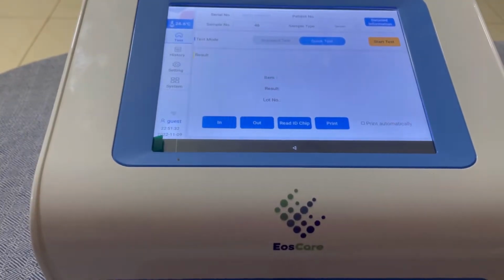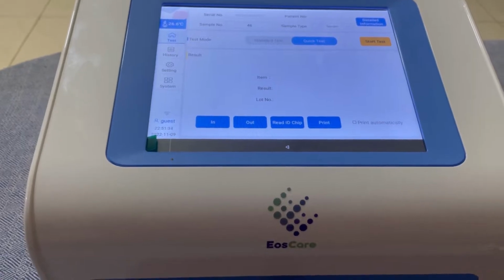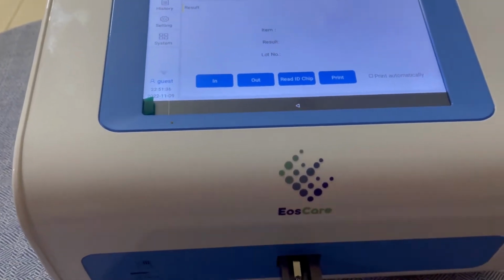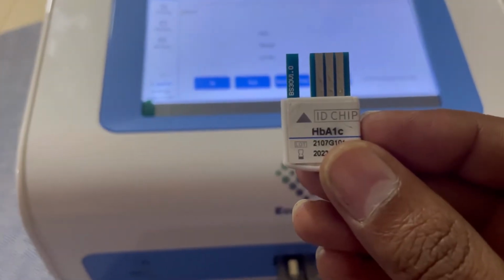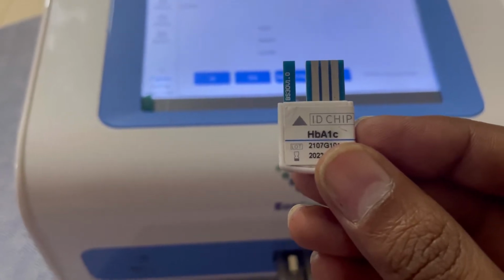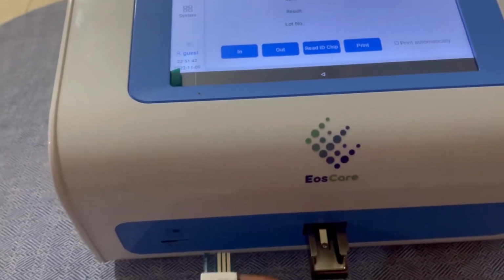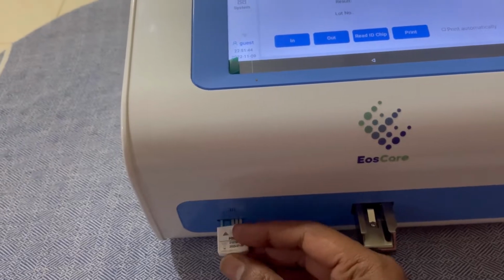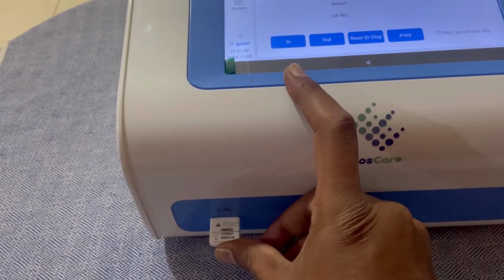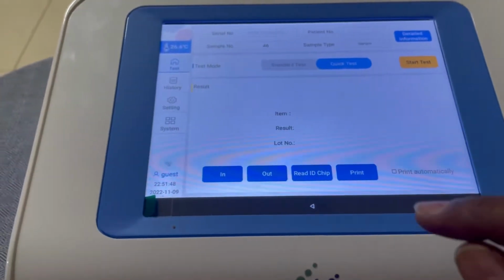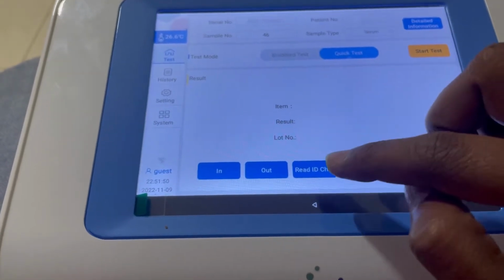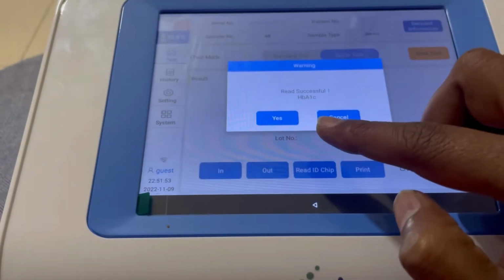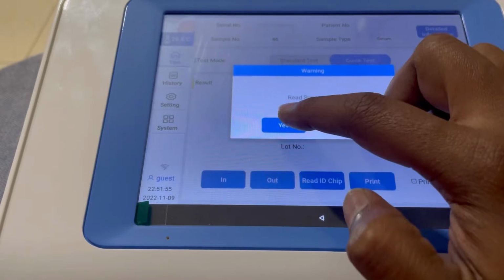While we have put the buffer and cassette for preheat, we will save the calibration. If you see, this arrow shows the way we have to insert the ID chip. So I am inserting it now. The ID chip has been inserted. Now I will click read ID chip. Your calibration has been read and saved in the instrument.